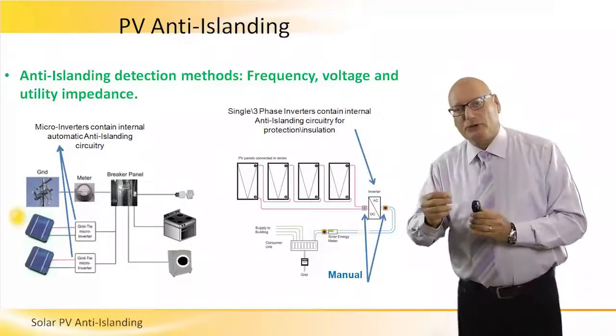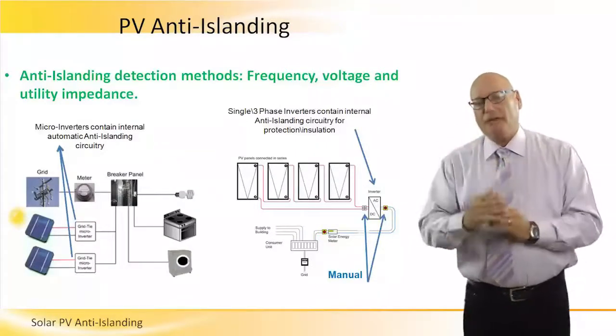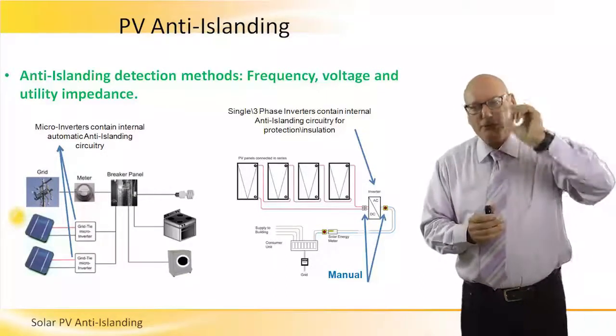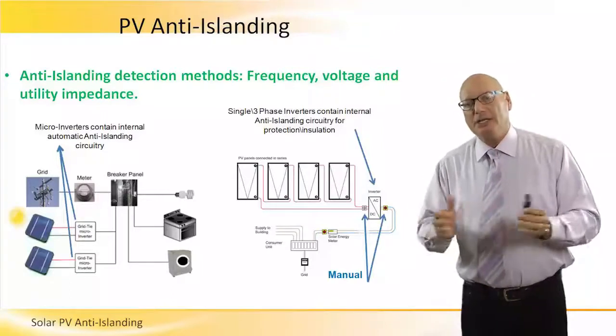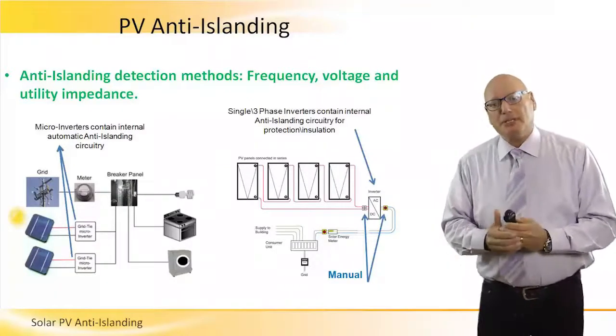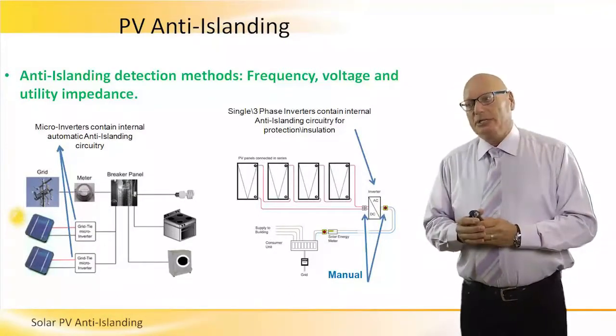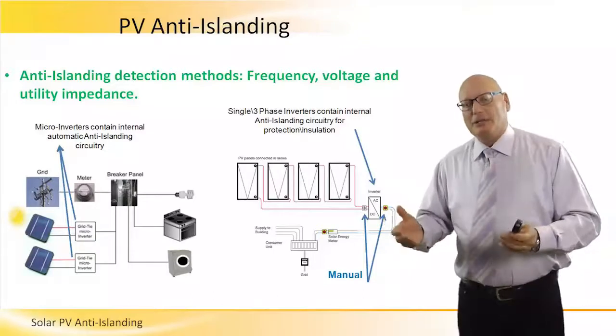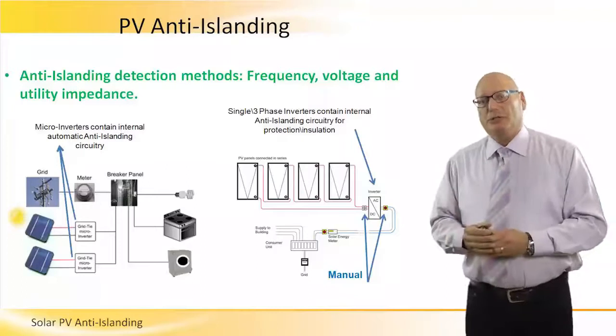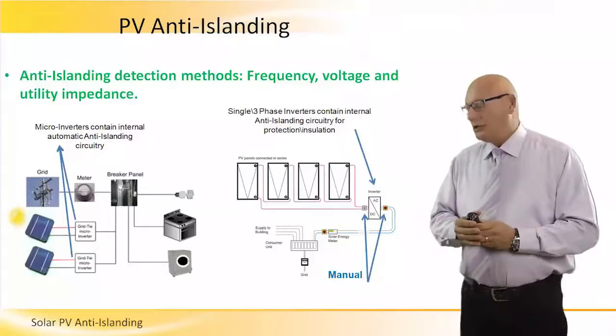Regarding voltage: if we are talking about a 230-volt AC grid, and the voltage goes above 230 plus 5 volts or below minus 5 volts, the anti-islanding circuitry will automatically split the system. Additionally, regarding utility impedance: if there is a cut-off in the grid — meaning there is high impedance on the cables and connectors — the anti-islanding circuitry will automatically activate.